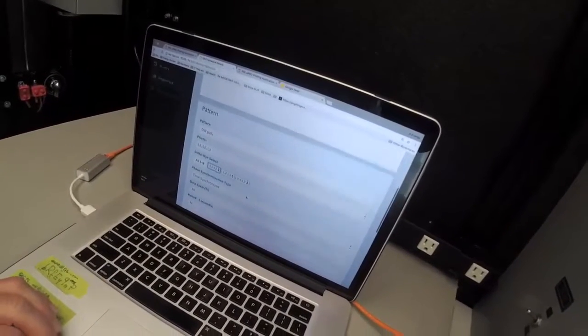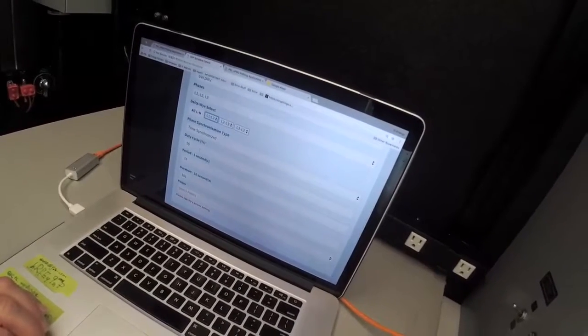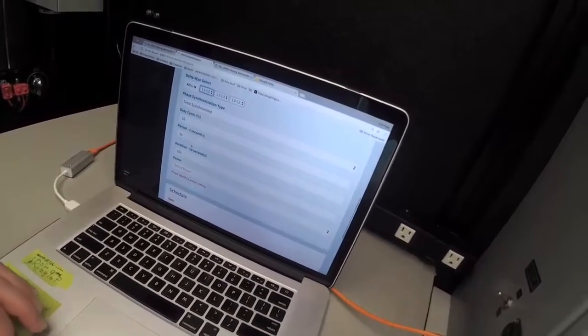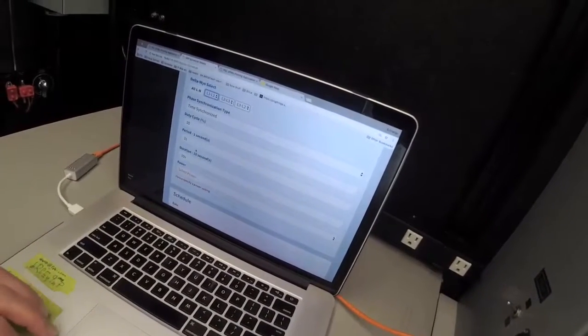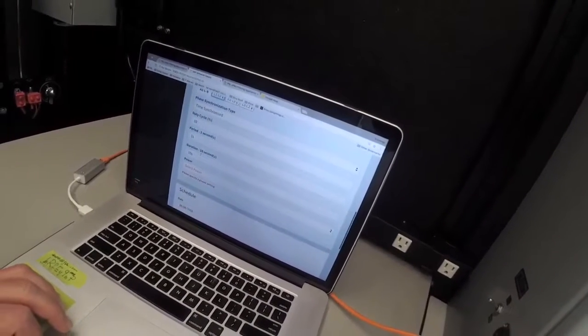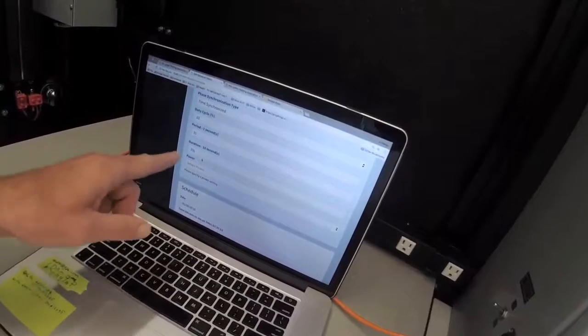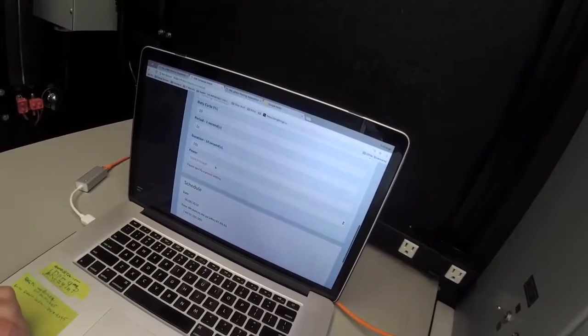The patterns are a pre-programmed set of sequences, including the phase-to-phase pattern we're using here, and a 10% duty cycle for this test with a period of 1 second. That means for the first tenth of a second the load will be engaged, and then for the next nine-tenths of a second it will be off, occurring 10 times for a duration of 10 seconds.